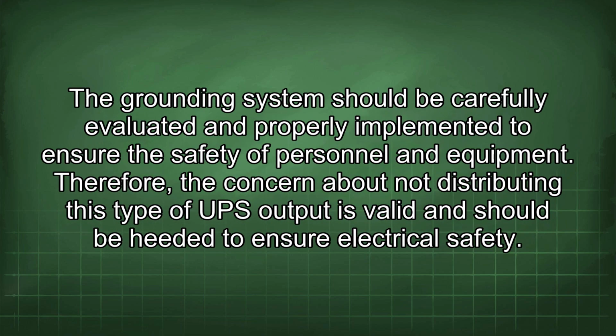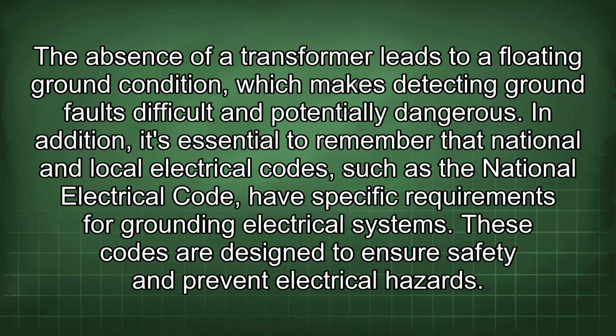The grounding system should be carefully evaluated and properly implemented to ensure the safety of personnel and equipment. Therefore, the concern about not distributing this type of UPS output is valid and should be heeded to ensure electrical safety. The absence of a transformer leads to a floating ground condition, which makes detecting ground faults difficult and potentially dangerous.